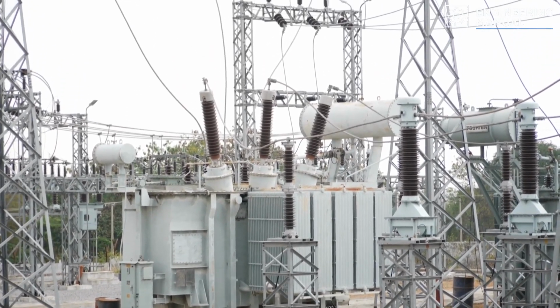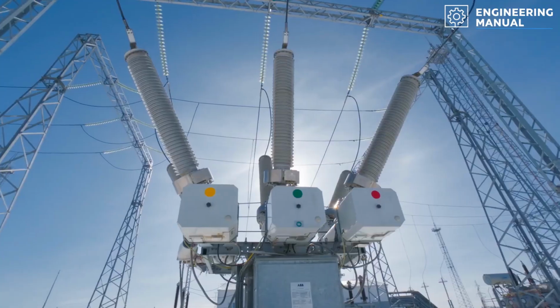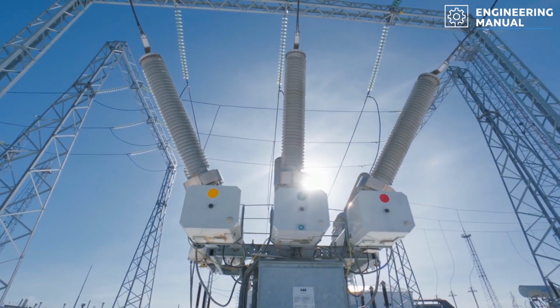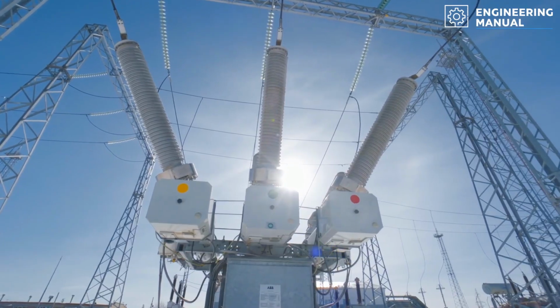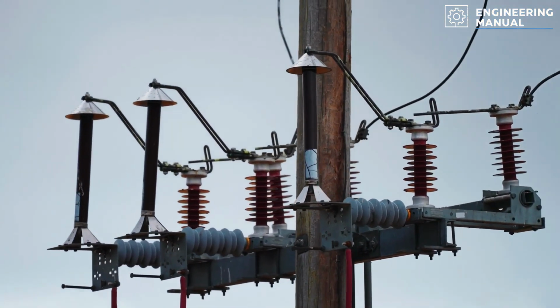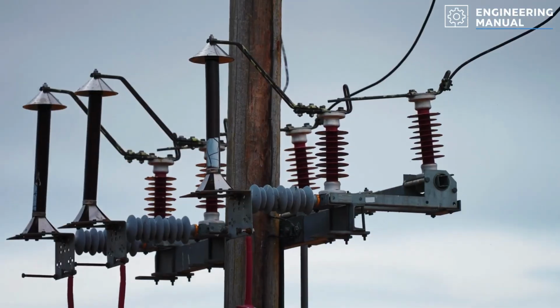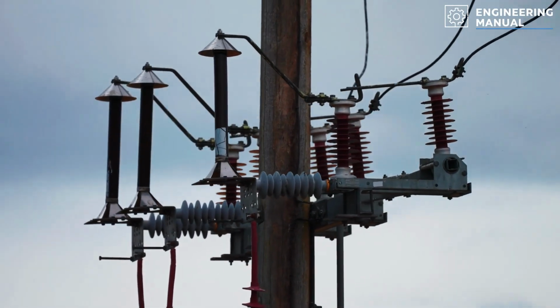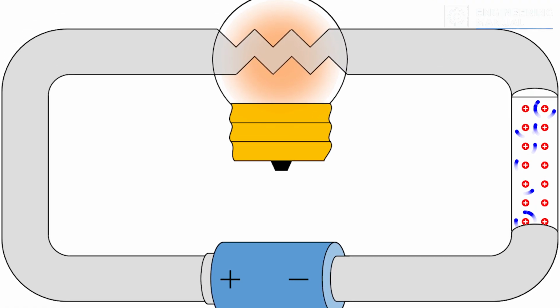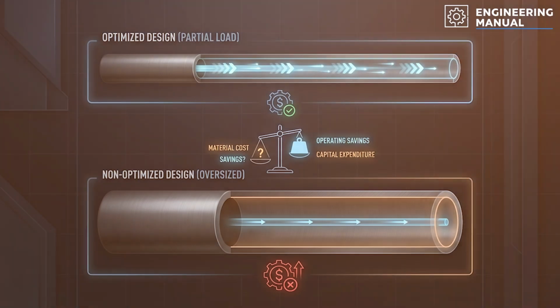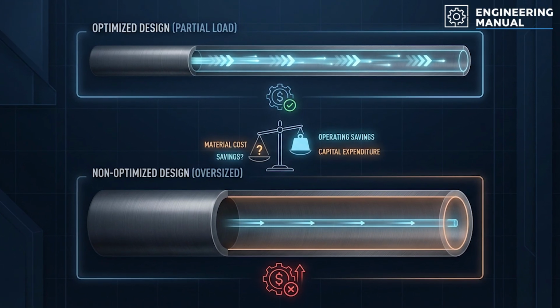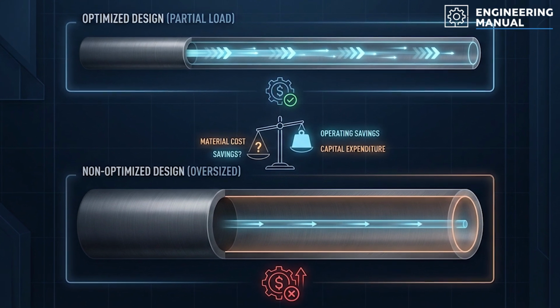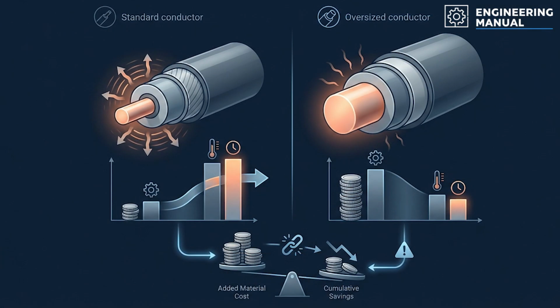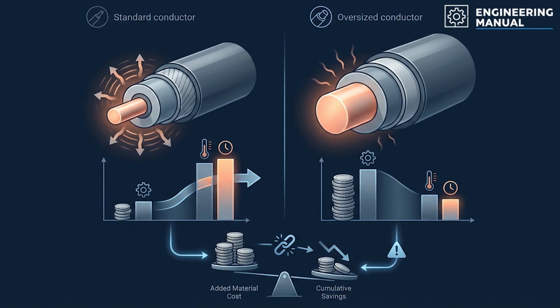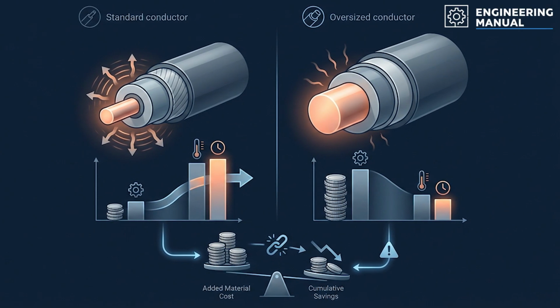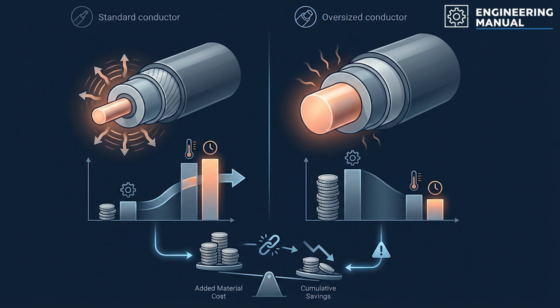In electrical engineering, oversizing transformers or conductors can reduce losses, but only up to a point that makes economic sense. The power lost in a conductor depends on current and resistance, often expressed as I squared R. So lowering resistance by increasing conductor size can reduce wasted heat. But if the system operates at partial load most of the time, then the savings from extra copper may never repay the added cost. In that case, the design is no longer optimized. It is simply carrying more material and capital than the operating profile justifies.